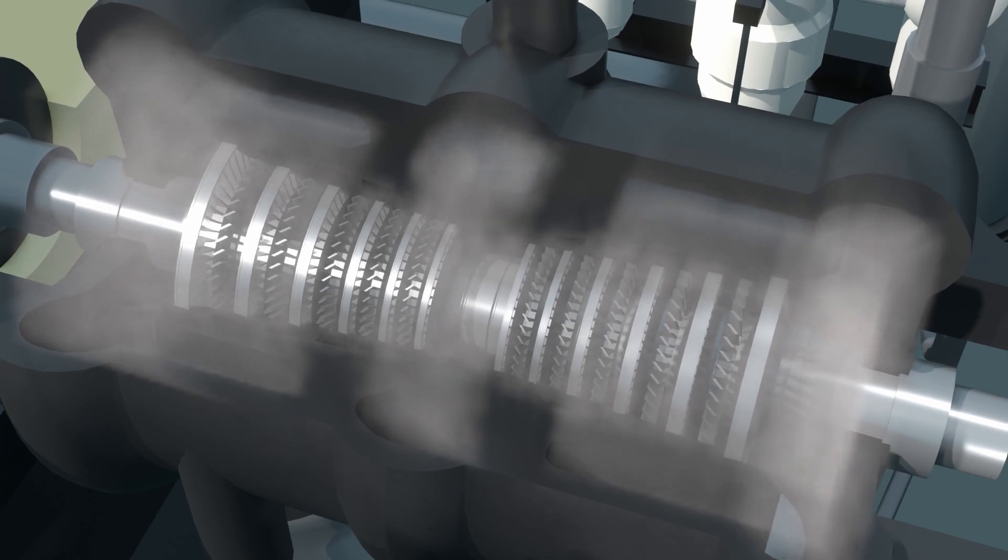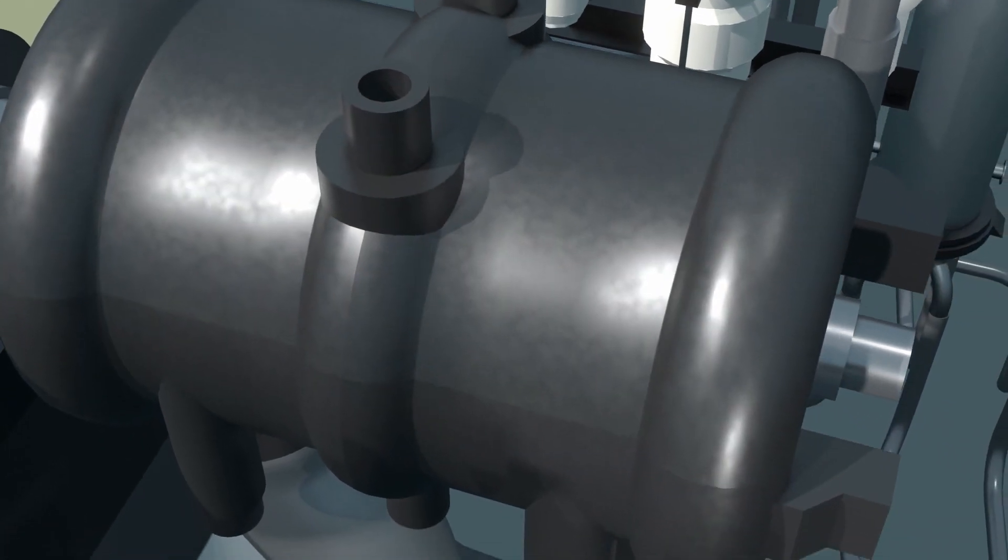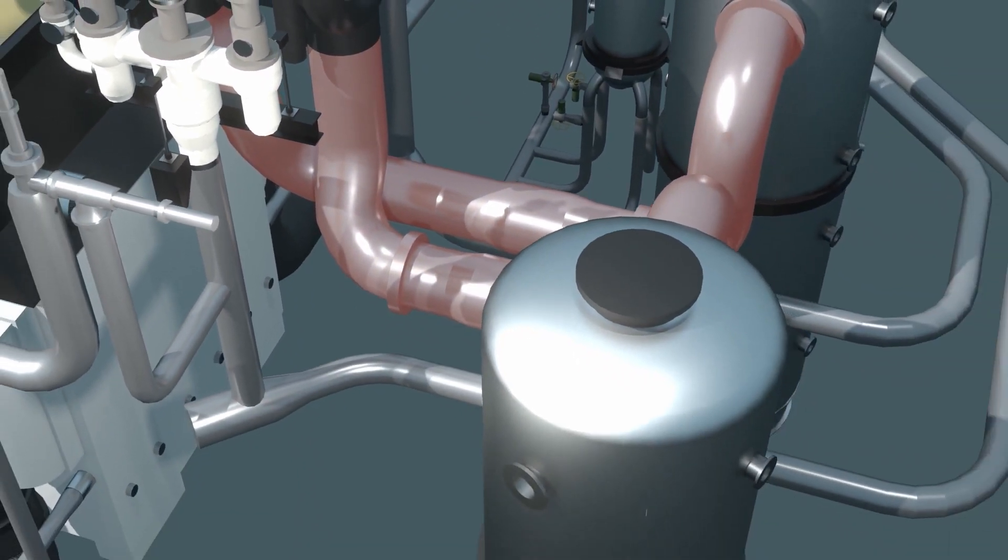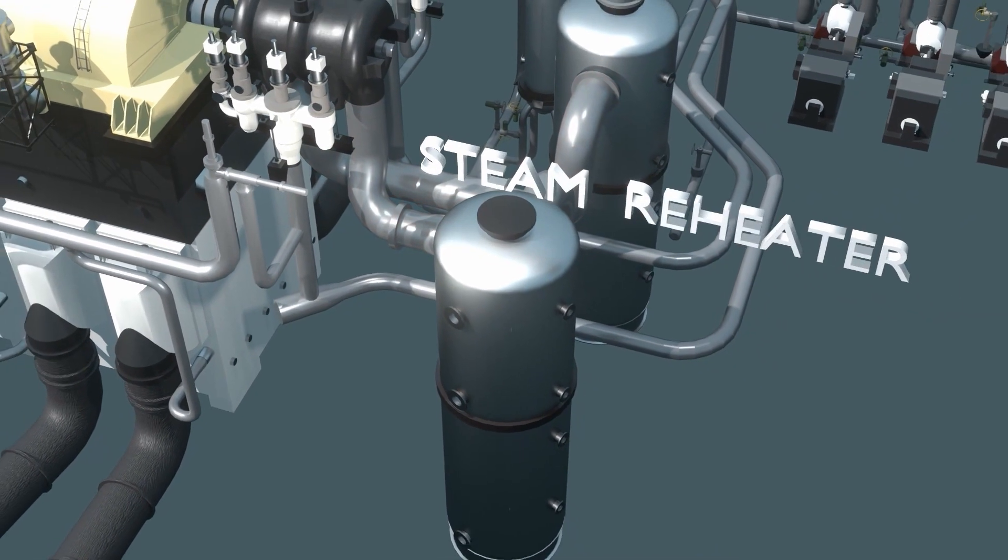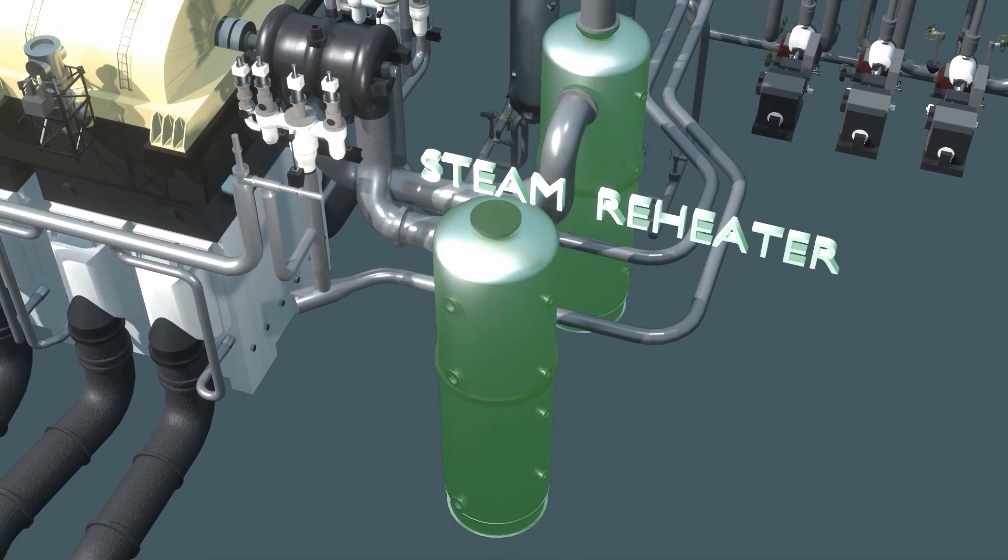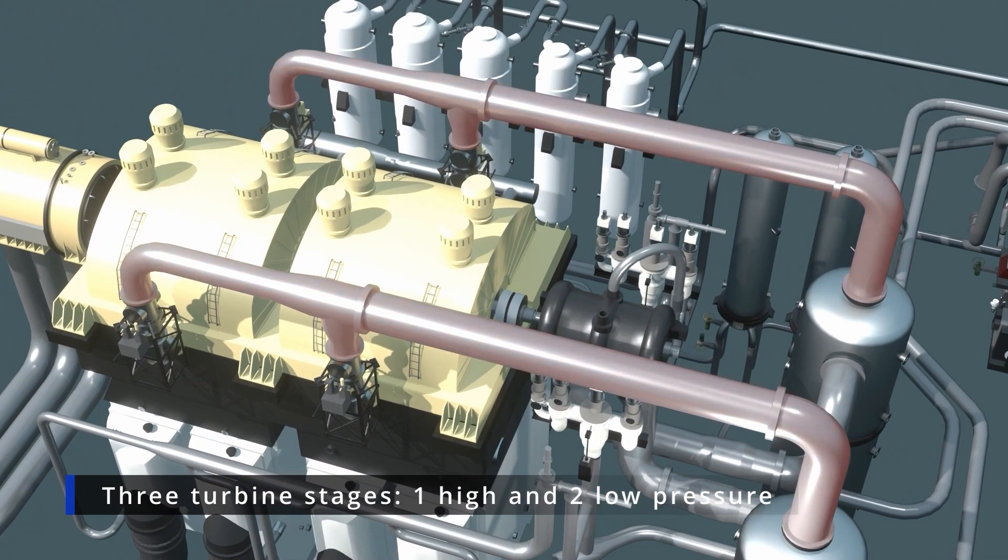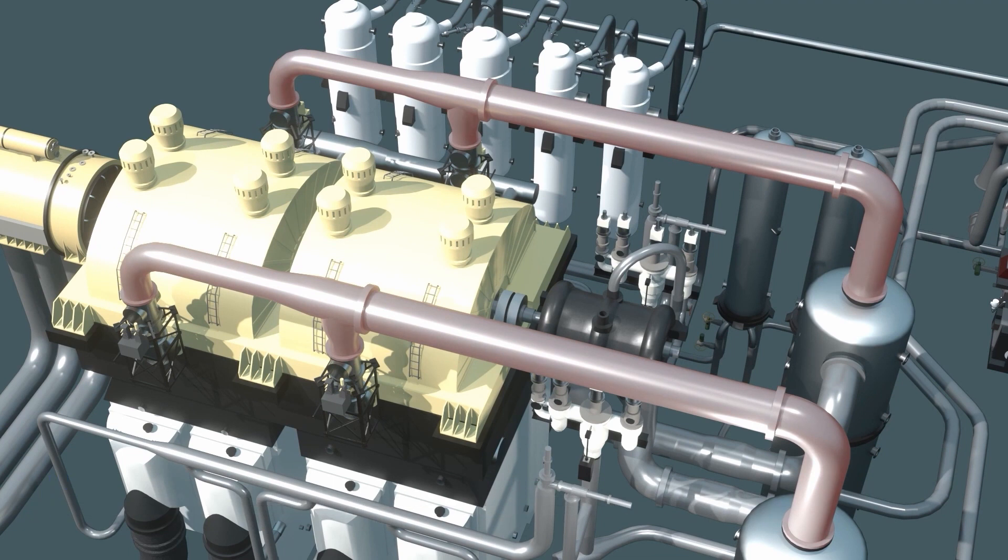It then passes into the steam separator and reheater, where water particles are separated, and the steam is heated. It then travels to the two low-pressure stages of the turbine, where it transfers the rest of its energy and spins the other turbine wheels. The blades of the impellers are much larger in the low-pressure stage of the turbine than in the high-pressure stage. This is how we make the most of the steam energy.